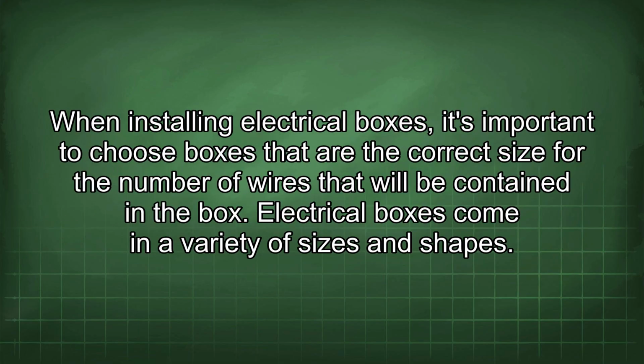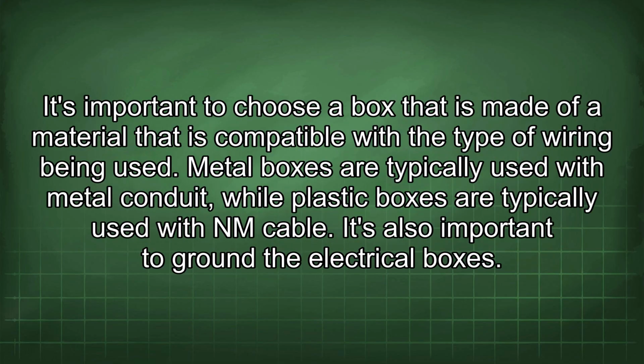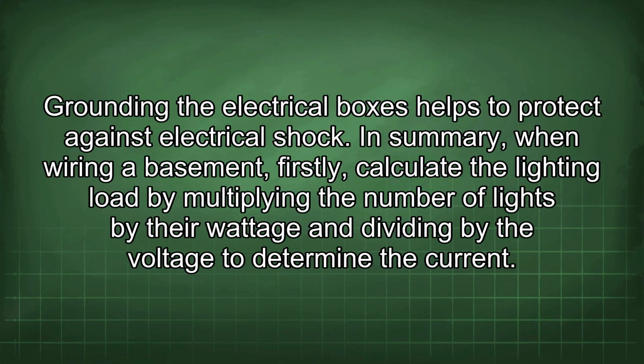When installing electrical boxes, it's important to choose boxes that are the correct size for the number of wires that will be contained in the box. Electrical boxes come in a variety of sizes and shapes. It's important to choose a box that is made of a material that is compatible with the type of wiring being used. Metal boxes are typically used with metal conduit, while plastic boxes are typically used with NM cable. It's also important to ground the electrical boxes. Grounding the electrical boxes helps to protect against electrical shock.